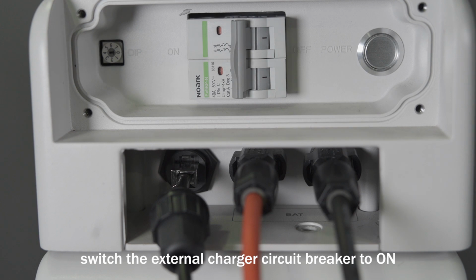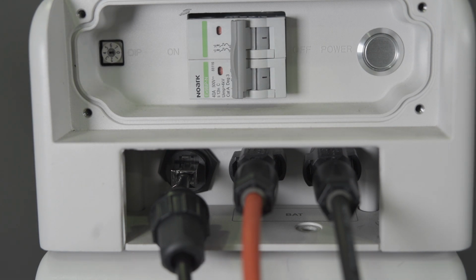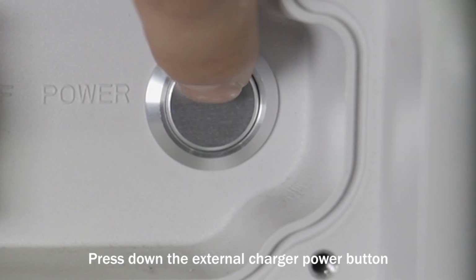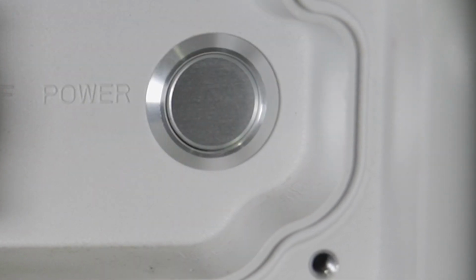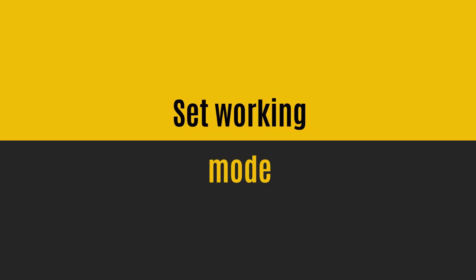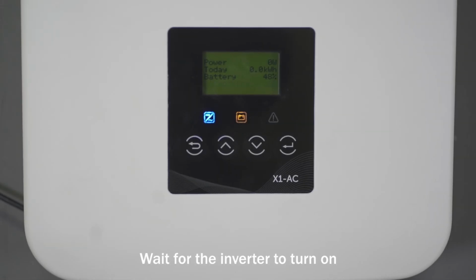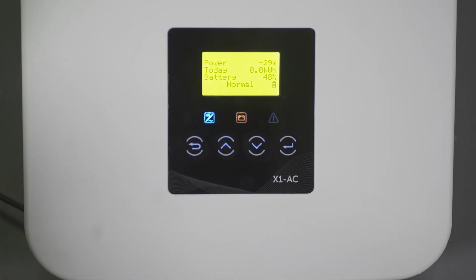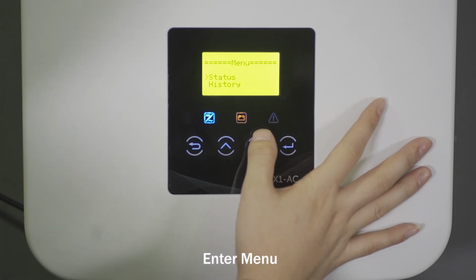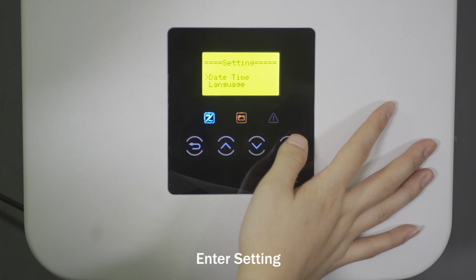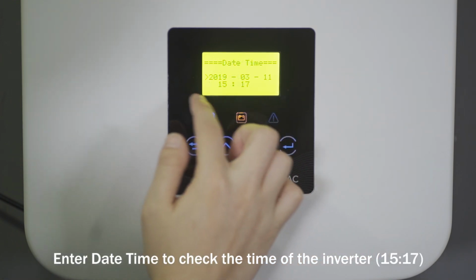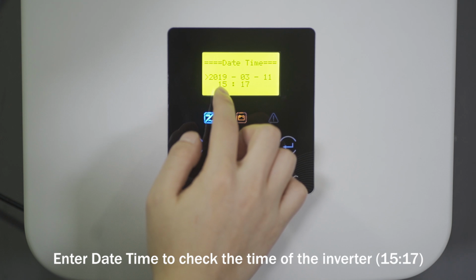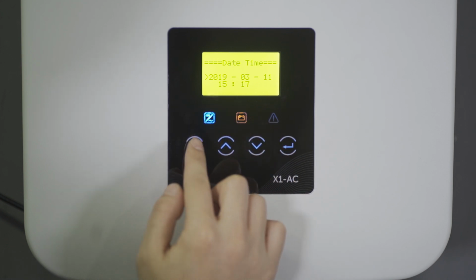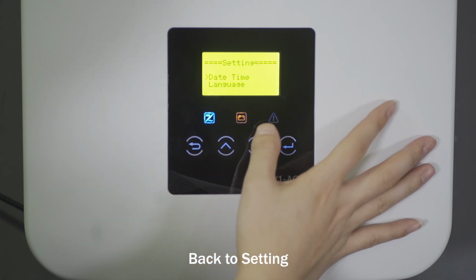Switch the external charger circuit breaker to on. Press down the external charger power button. Wait for the inverter to turn on. Enter menu. Enter setting. Enter date time to check the time of the inverter. 15:17. Back to setting.